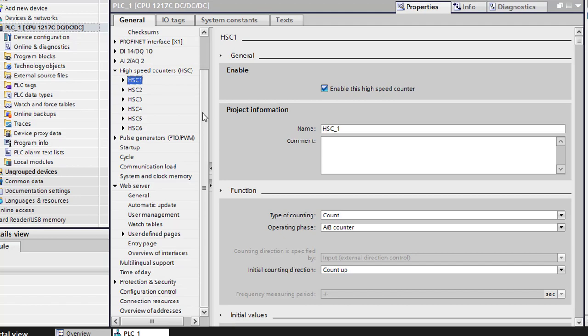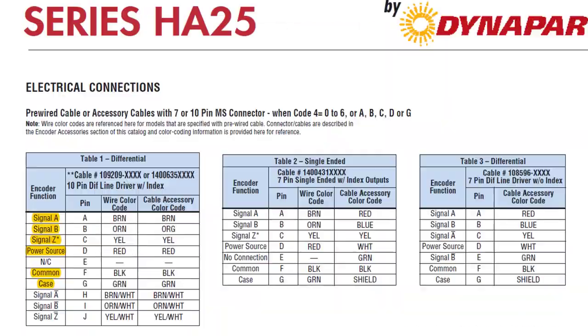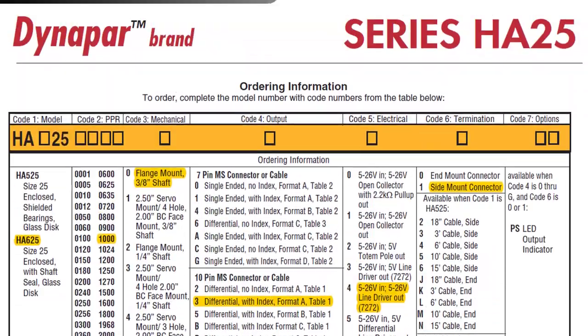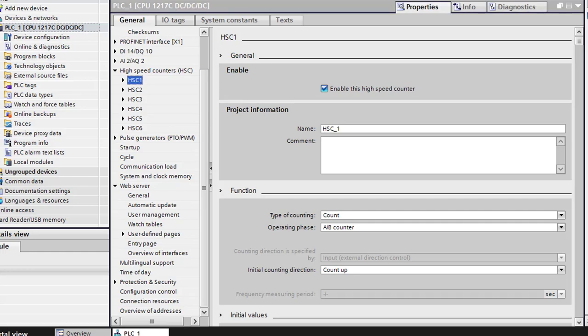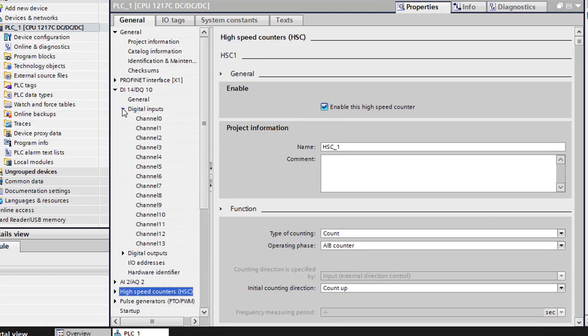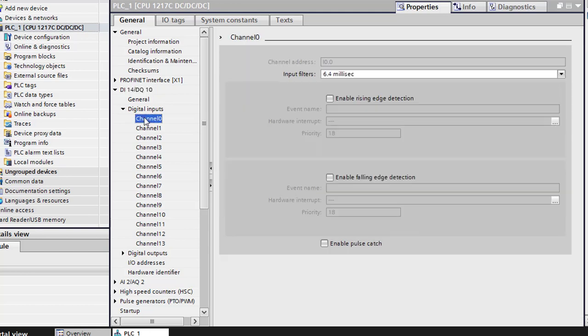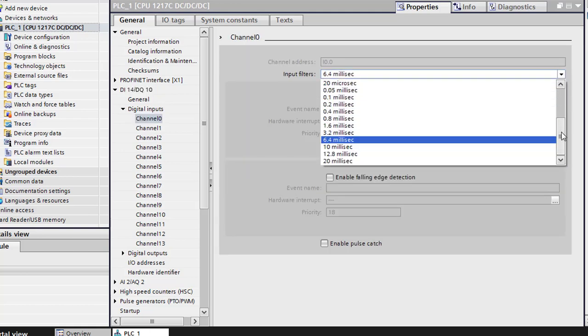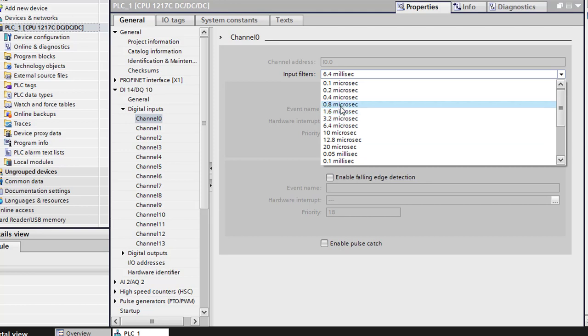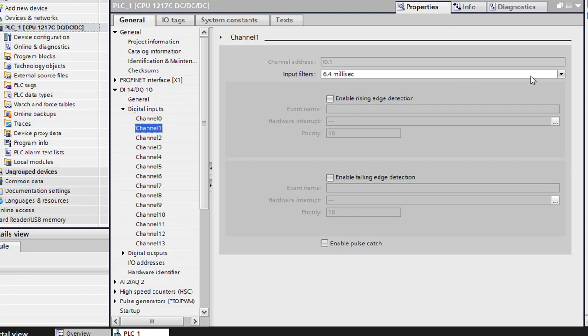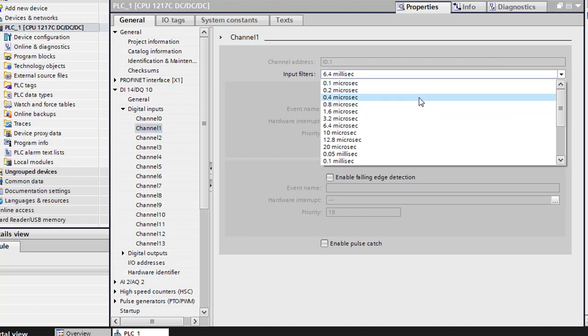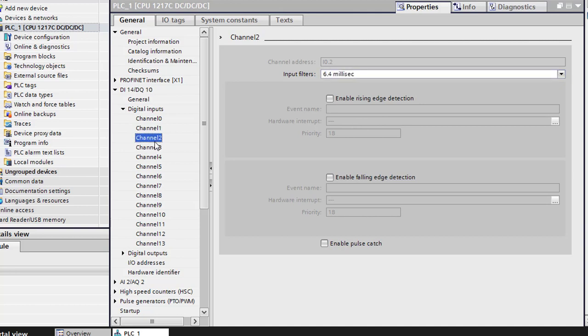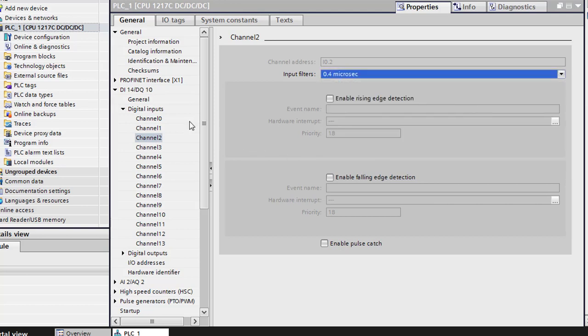Okay, hardware outputs we're not going to worry about. IO address, this is important. So when we go back to look for this count value, it's going to be an ID 1000. The hardware identifier is 259, and I'll show you where that plays a role here soon. Okay, now the next important thing that you're going to want to do: when we went on to the PDF here, we scroll back up the screen to our highlighted section at the top where it says the rise and fall times are less than one microsecond. We'll go back in here. We'll go ahead and collapse high-speed counters, but we do need to go to our digital inputs. We'll come down to our inputs. We'll go to our first input or channel 0. We need to change that so that's less than one microsecond. So it looks like to be conservative we'll use 0.4. The next input or channel, we'll do the same thing.